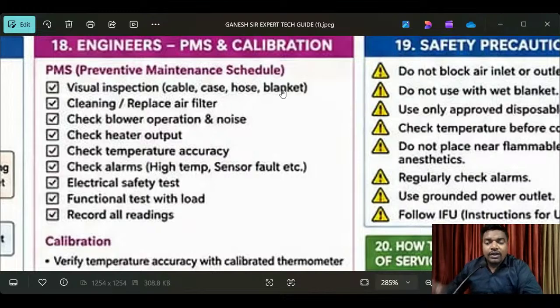When you are doing the PMS on medical equipment, you have to observe what? Visual inspection of cable, case, hose, blanket for the patient warmer. Okay. Now come here. Cleaning or replacing the air filter. Check blower operation and noise, check heater output, check temperature accuracy, check alarms such as high temperature, sensor fault, etc. And electrical safety test and functional test with load, and record all readings. Okay, these are the mandatory recommended points while doing preventive maintenance of the patient warmer.